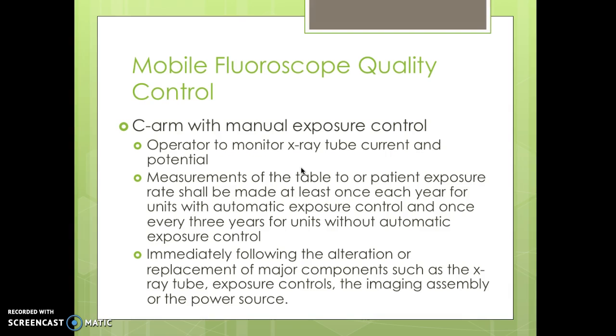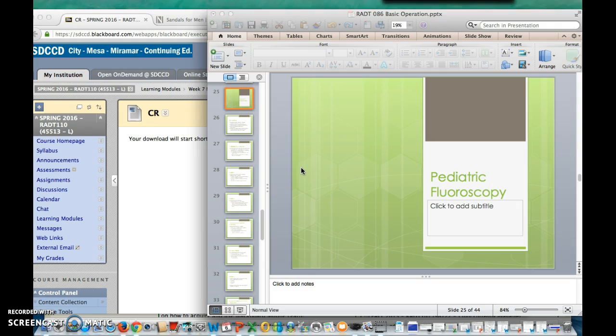For the C-arm with manual exposure control, the operator monitors the X-ray tube current and potential. Measurements of the table or patient exposure rate shall be made at least once a year for units with automatic exposure control, and once every 3 years for units without automatic exposure control. Immediately following the alteration or replacement of major components like the X-ray tube, exposure controls, image assembly or power source, you have to bring a physicist out at that point.